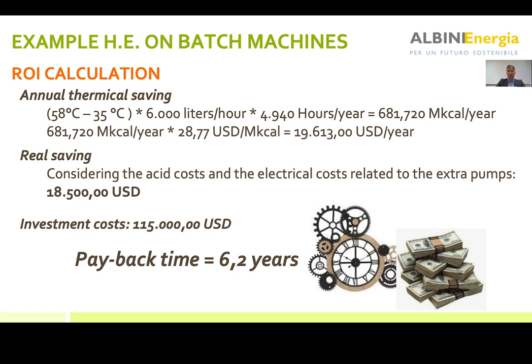Over here you can find the savings. The saving is mainly related to the thermal energy that you can save because you have warmed the temperature of the second and third rinsing - the reusable water from 35 degrees to 58 degrees. You have to multiply such a difference by 6,000 liters per hour and the number of hours per year, which are almost 5,000.